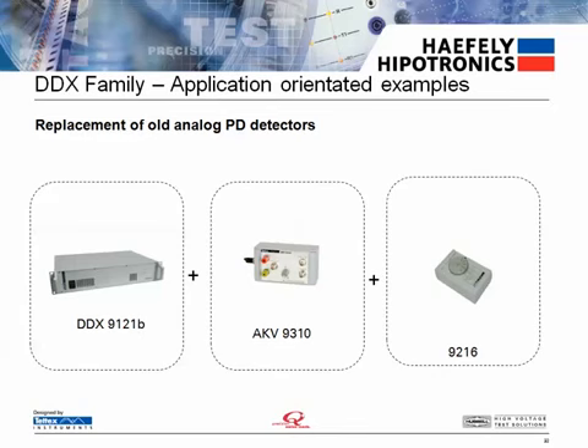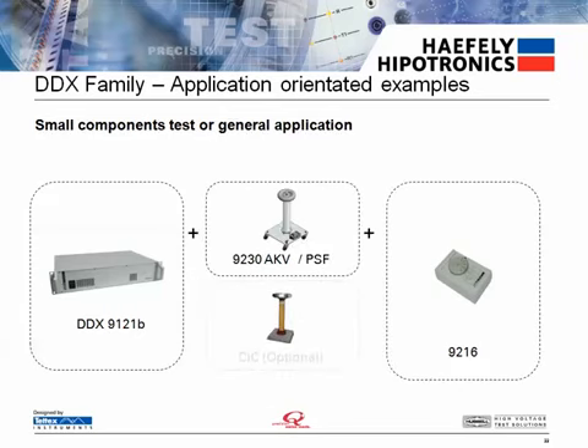If you have an existing PD test system and are looking to upgrade the detector, we will offer our DDX9121B along with an AKV 9310 measuring impedance, which will replace the low arm of your existing coupling capacitor, along with a 9216 calibrator. For cases requiring a new test system, we will offer the DDX9121B with either the 9230 or PSF coupling capacitor and a 9216 calibrator. And of course, we can also offer the high voltage test source.